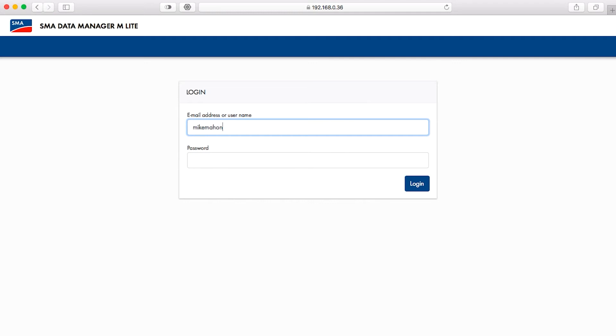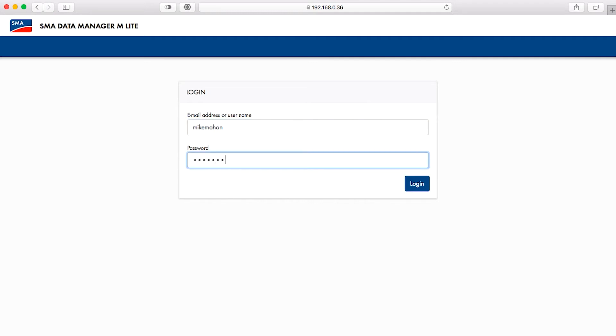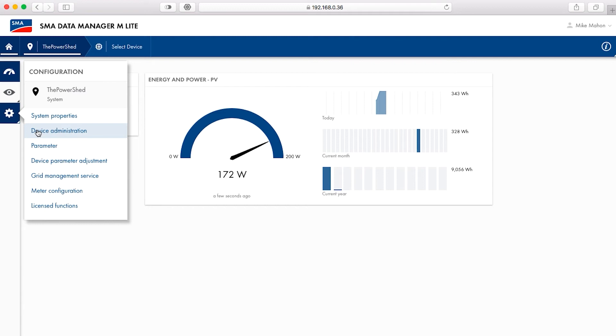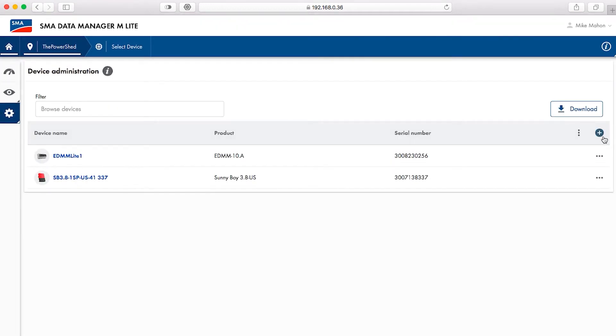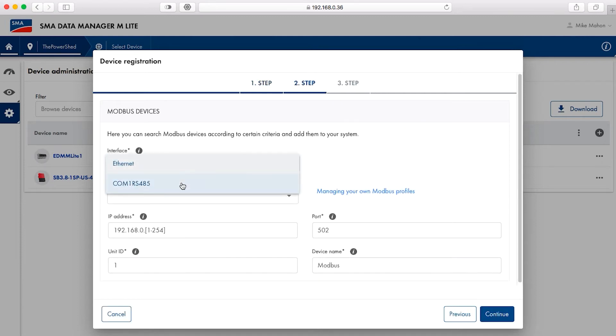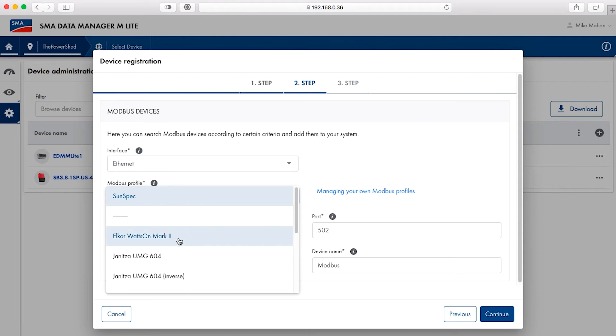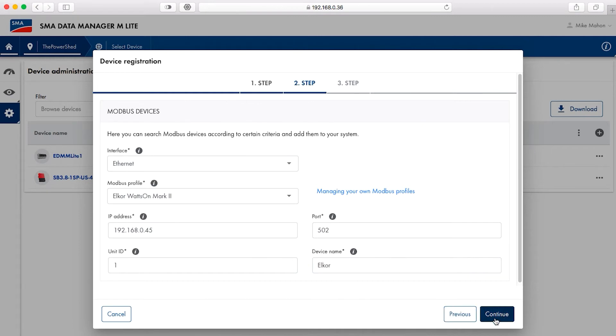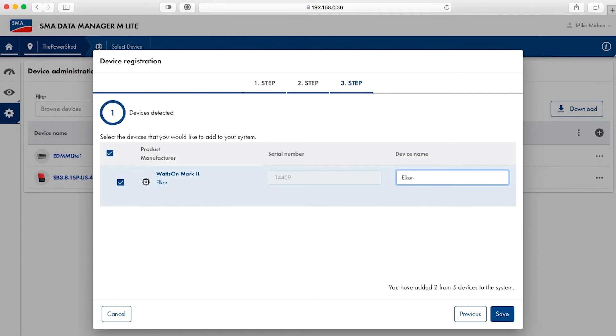The login credentials for the user interface are those set during the original commissioning of the data manager. Once logged in, select the configuration or wheel icon from the list on the left and select device administration from the list that appears. In the pop-up window that appears, select the plus sign at the top right. Verify the radio button next to Modbus devices is selected and then click continue. Select ethernet from the interface drop-down menu. Select Elkor WattsOn Mark II from the Modbus profile pull-down menu. Enter the correct IP address for the meter in the IP address window. If needed, change the Modbus port from the default 502 value. Leave the unit ID as 1. You may change the name if desired. Select continue when done. Select the radio button next to the meter and adjust the device name if desired. Select save when done.